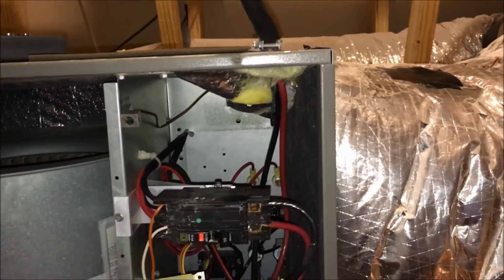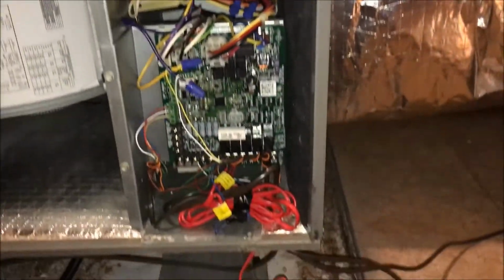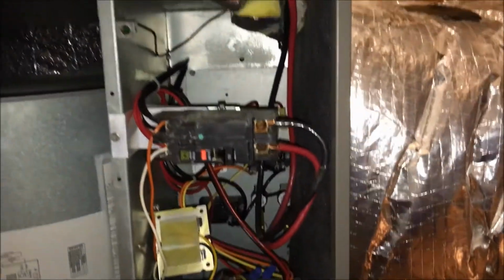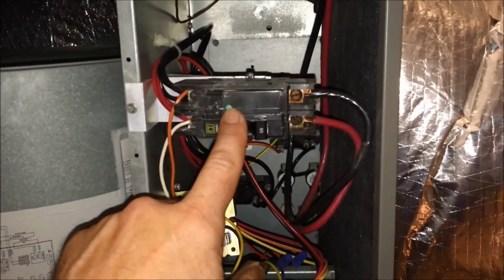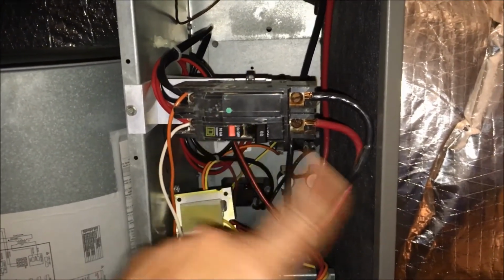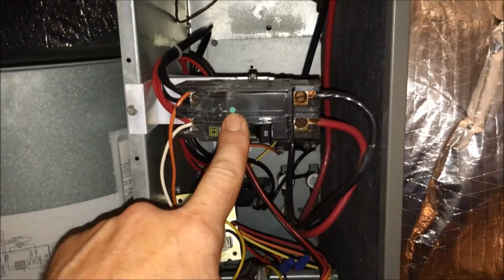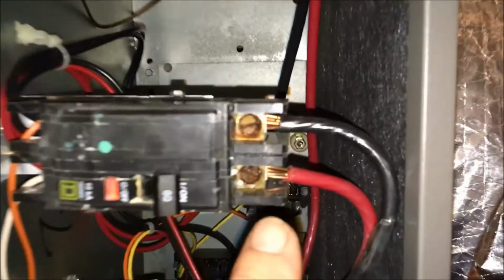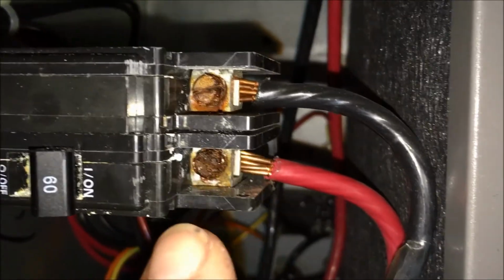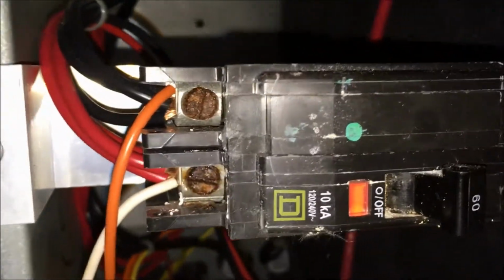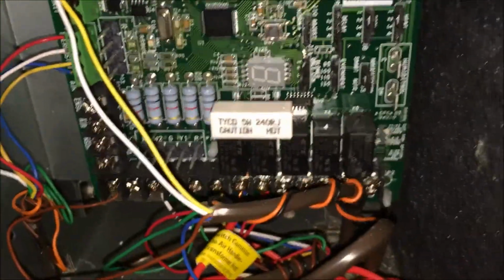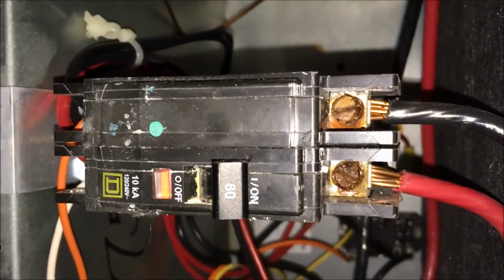I've taken the panel off my Lennox air handling unit and just doing a general investigation. I was having problems with this breaker. I had to flip it off and then back on, and then the system started working, and then it stopped working again. But look what I've determined here. The corrosion around this breaker is terrible. So I'm going to get a new breaker. I don't see any other indication of problems here. So I'm going to see if I can't fix this myself without having to call in the HVAC people.